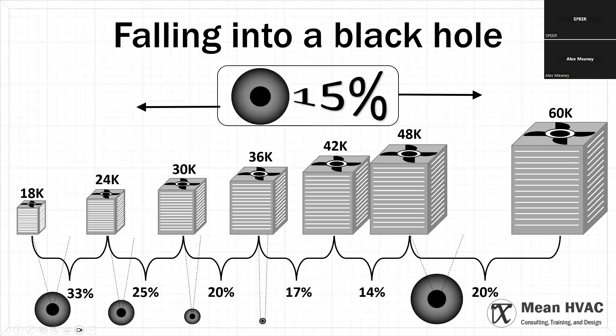The next edition of Manual S, if things continue as they've been, will allow loads under 24,000 BTUs to be oversized by 20%, in addition to the 15% rule. There will also be more complicated methods for appropriately sizing equipment, but mostly having to do with heat pumps, particularly in cold climates, so it won't be much of a thing in your area.